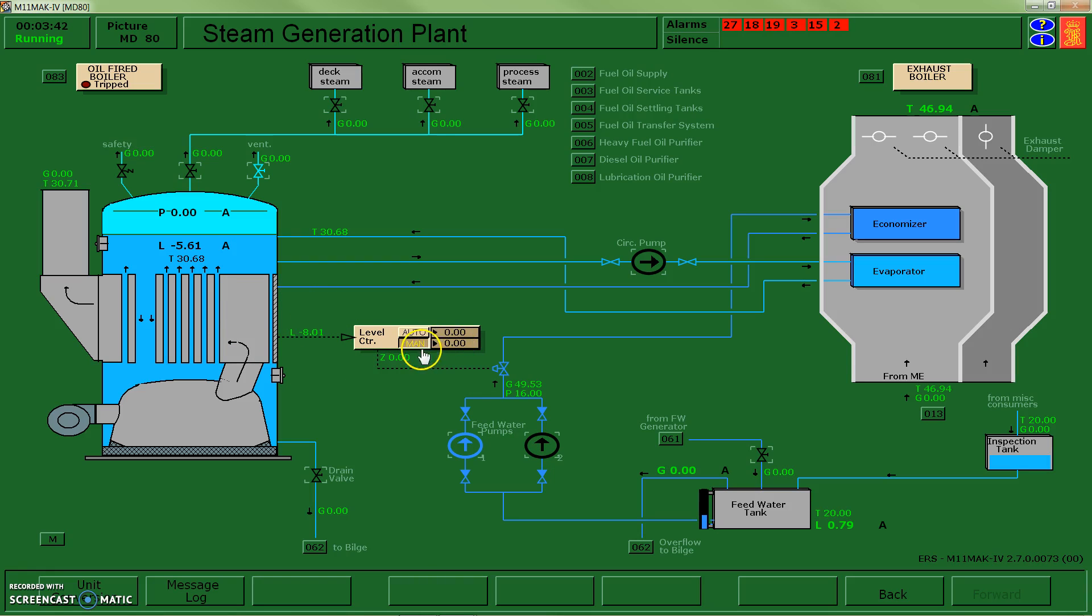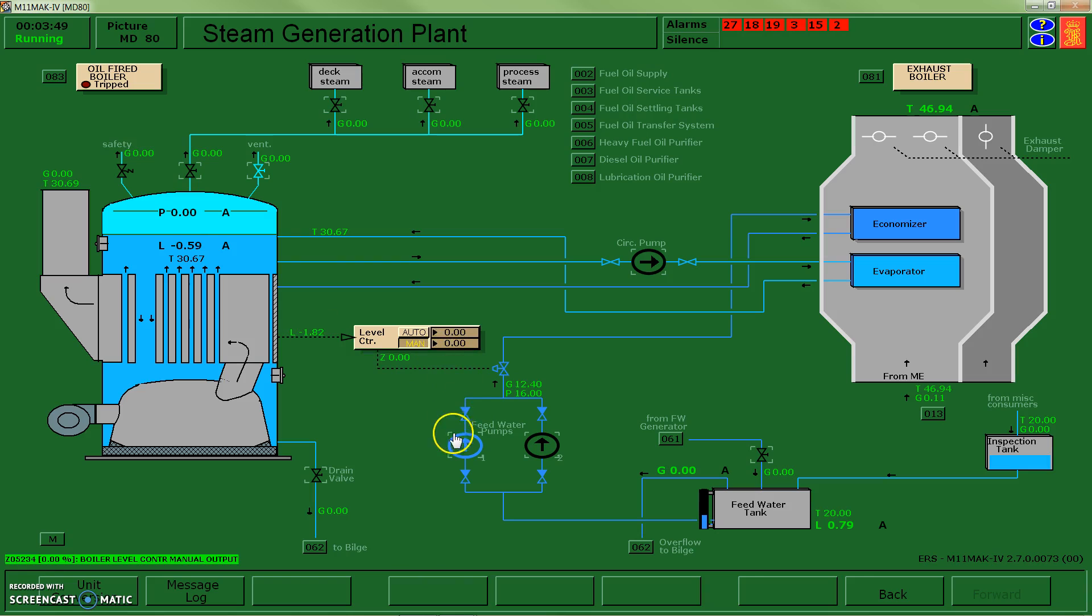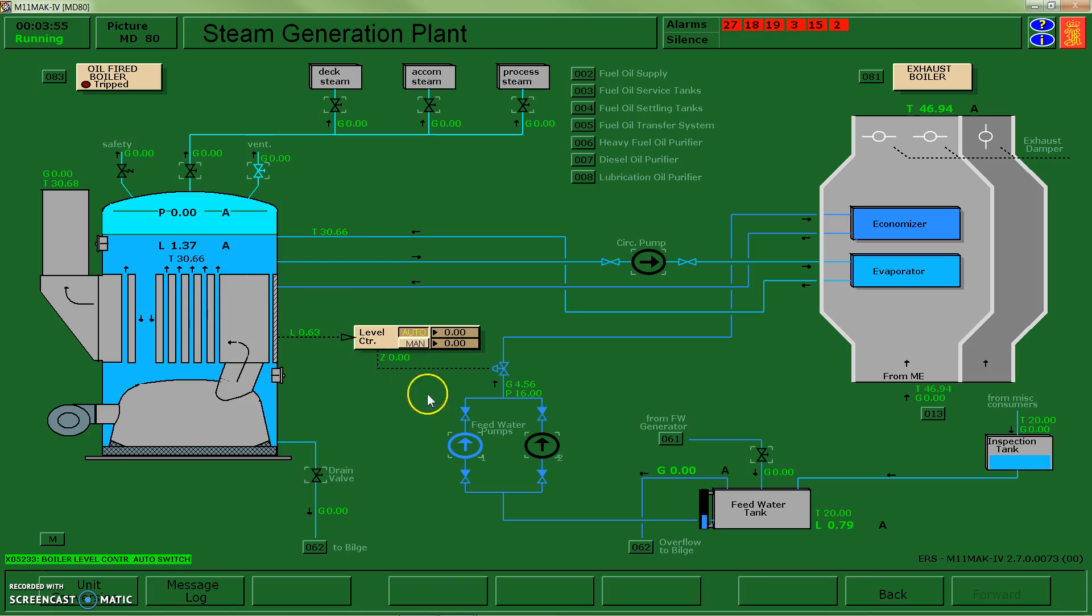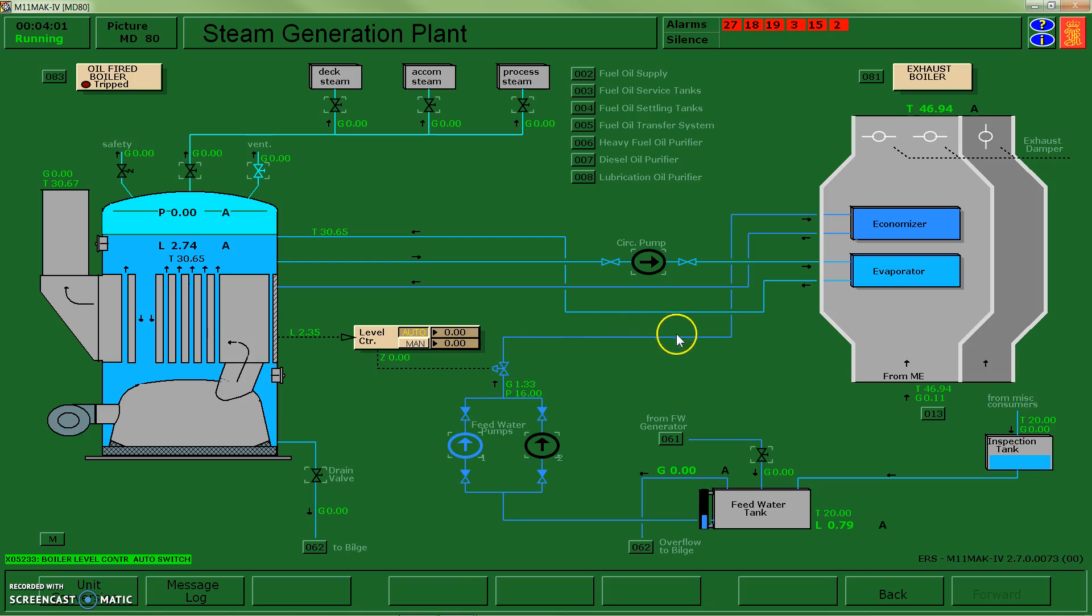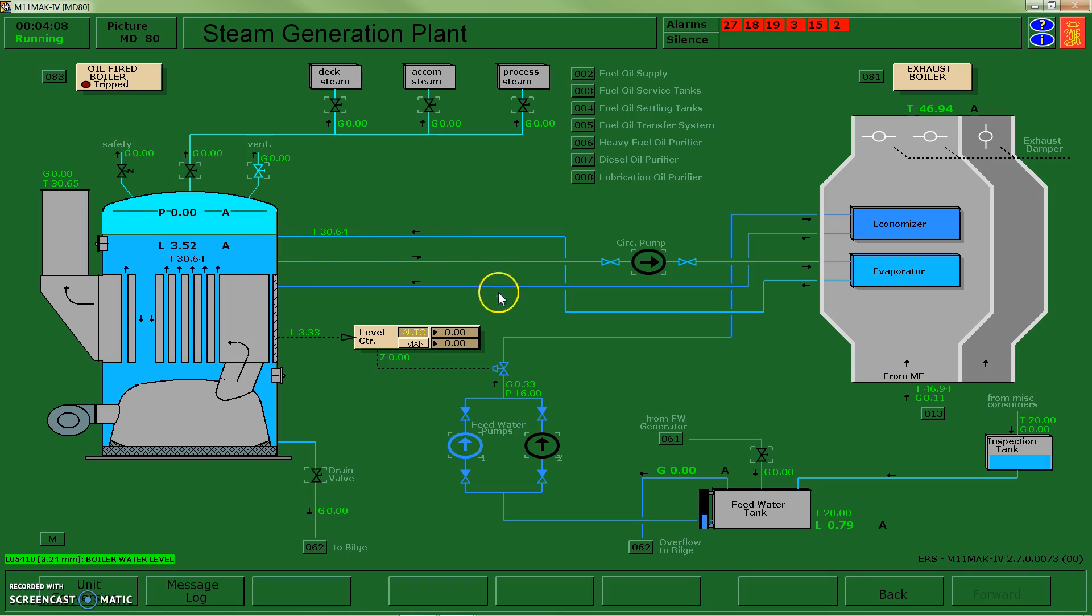Now I manually close the valve, I'm down to about zero. What I'm going to do is, now that I'm pretty close to zero, I'm going to switch my level controller over to auto. My pump is left on, and so when the boiler starts to demand water because the level starts to drop as I make steam or vent, the pump will be automatically able to keep up the level.